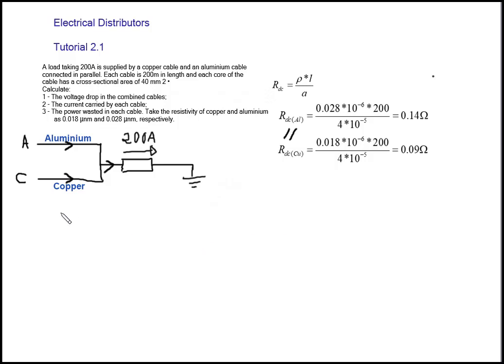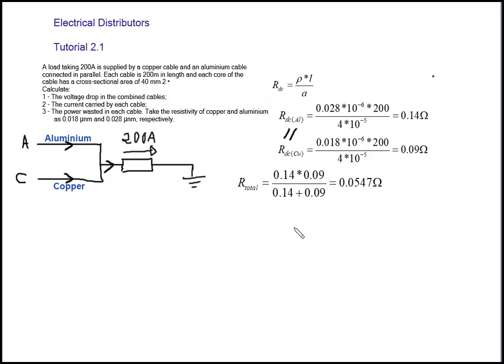Now that we have the resistance of each cable, the next step is to find the total resistance of the combined cable, since we need the voltage drop of the combined cable. We can use the current divider rule once we have each cable's resistance, but we still need the total parallel resistance. Combining aluminum and copper in parallel gives R_total = 0.0547 Ω.